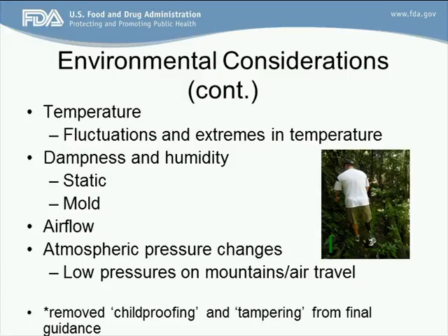You want to look at temperature fluctuations and extremes. And this I'm talking about, let's say you're going from a very warm environment out into the cold to get into your car. Are you going to have problems with condensation? Are there other issues that could happen if you are out in the heat for a very long period of time with your device? And just think of those different things as you're designing the device, what it is that might be necessary for a temperature fluctuation.